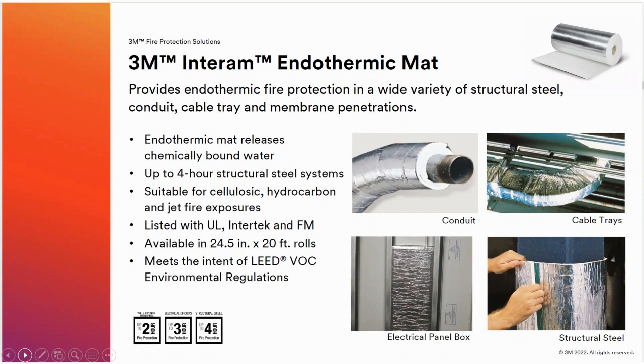And then the last product I'm going to talk about here is our endothermic mat, or EMAT as it's known. So this material is a flexible wrap system that utilizes our endothermic technology. So basically it relies on chemically bound water. As this material heats up in a fire, the chemically bound water is slowly released, which has a cooling effect on the surface of the material. We have tested systems with this product for 2, 3, and up to 4 hours on structural steel. It can be used to wrap conduit and cable trays. You can also use it on the backside of electrical panel boxes. And of course, it's UL, Intertek, and FM approved.